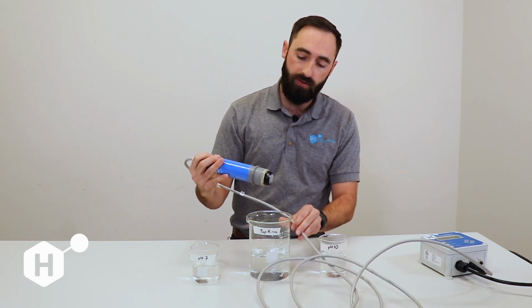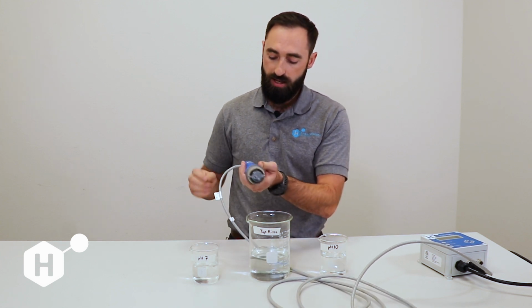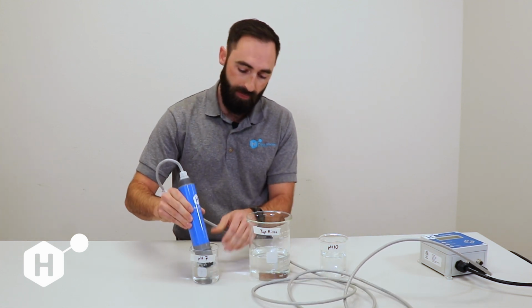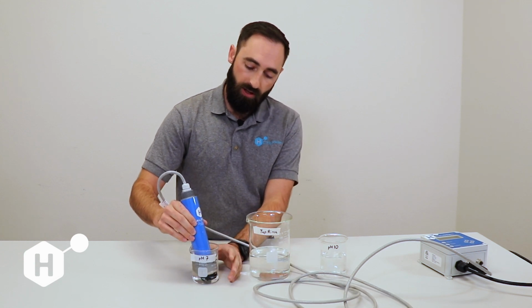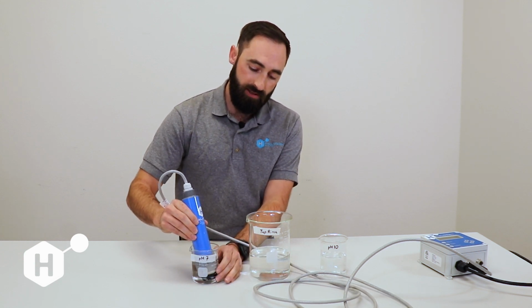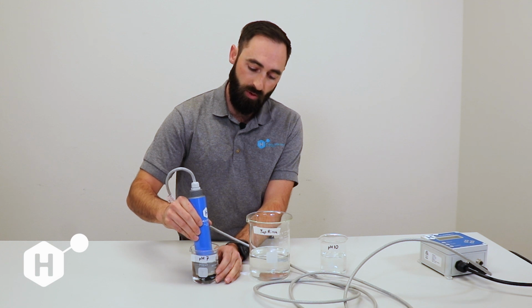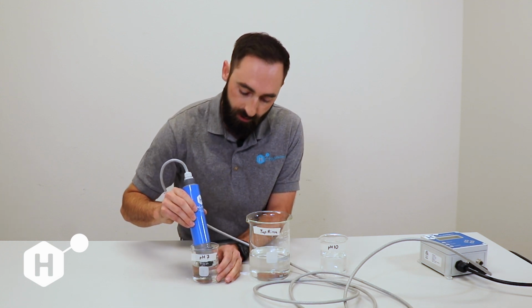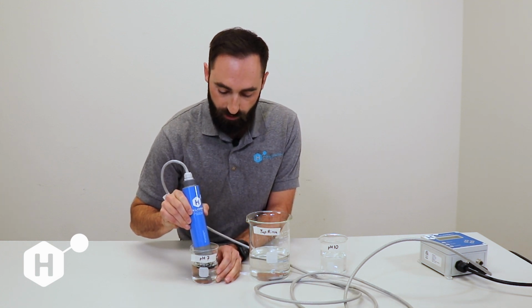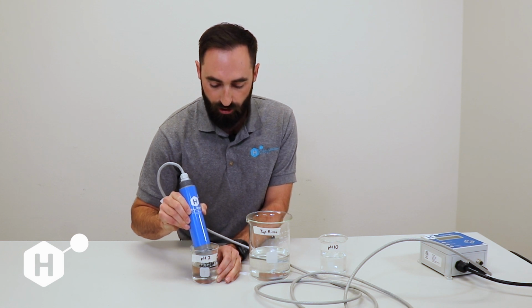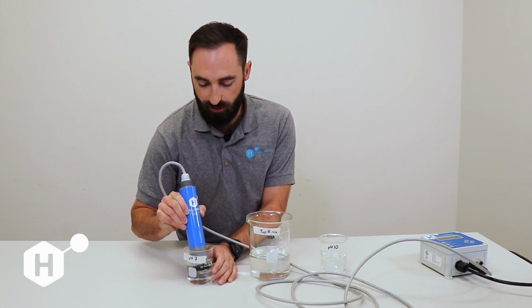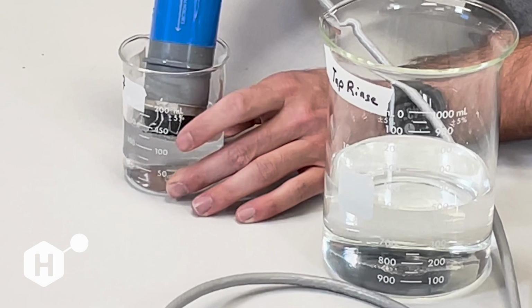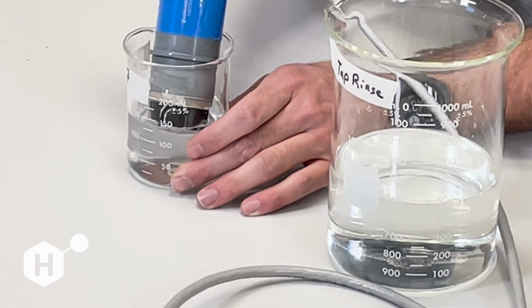And then we're going to move the sensor, keeping note of where the ejection port is, into our buffer here. Now a lot of the times the sensor is not going to prime itself, and you might have to give it a little swirl to re-establish flow. Before we do any sort of calibration, you're going to want to check and make sure that you can see visually that we have pH buffer flowing out of our ejection port.